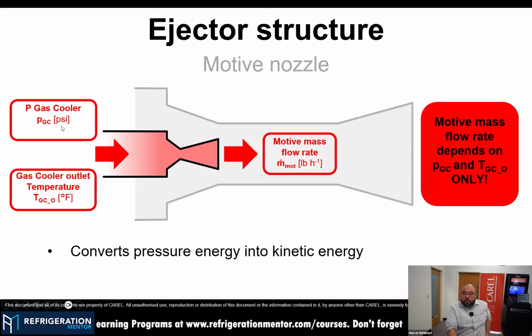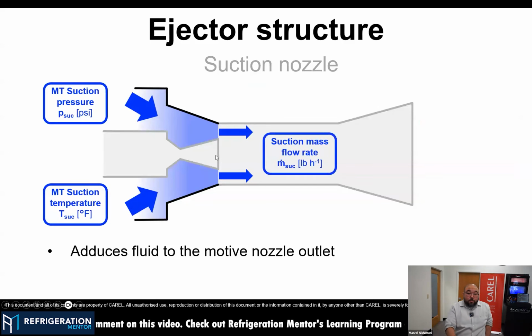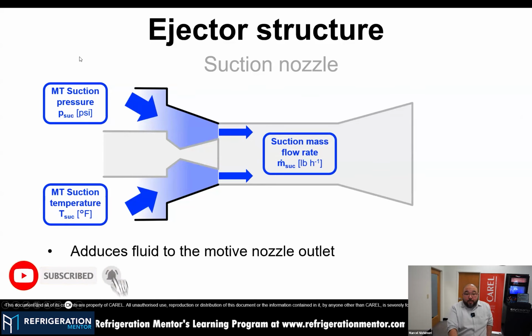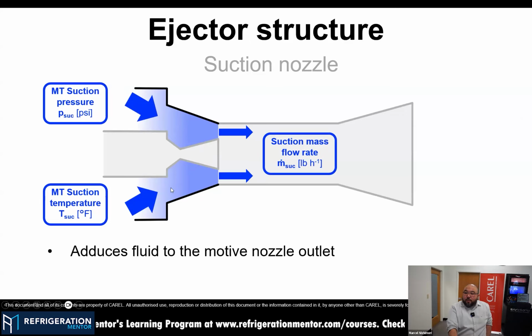Okay, so I have a refrigerant with high pressure and normally high temperature passing through an expansion, because the high pressure valve is an expansion device. During this expansion, we are also increasing the speed of the refrigerant. So I create a mass flow with high refrigerant flow that generates some dragging effect. On the other port, the suction port, coming from the medium temperature suction line, we have a refrigerant at, let's say, around 400 psi as a pressure for medium temperature applications. And when I make that expansion, I generate at this area, as you can see here, a low pressure zone, and the refrigerant, like current, will always go to the easiest path. So if the pressure is lower here, it will prefer to go through this path.